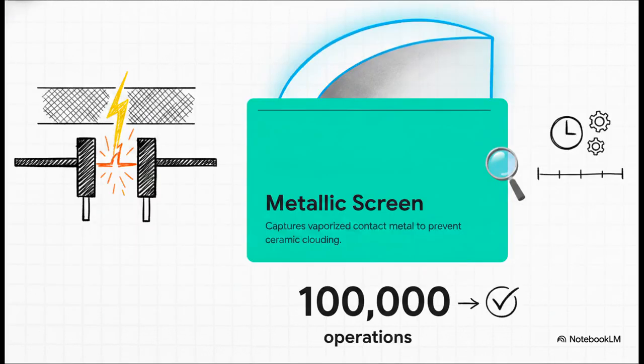And right here, we find the true hero of the bottle, that metallic screen. You see, every single time those contacts open under load, an arcing event vaporizes a microscopic amount of the contact metal. Without this screen, that metal vapor would eventually settle on the inside of the ceramic housing, clouding it over and destroying its insulation strength. But the metallic screen catches that vapor, keeping the ceramic clean and strong over decades of use. It's the exact reason that 100,000 operations is a reality, not just some marketing claim.